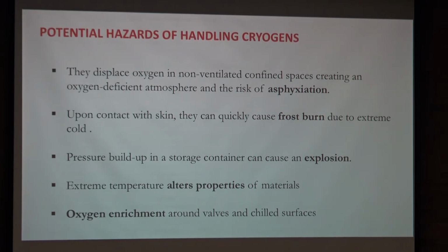When there is liquid evaporating, expanding into gas, and this gas cannot escape, then at some point you get into the regime where you run the risk that the vessel is actually exploding. Some of you may remember the Halloween tour we had a couple of years ago, where the building had to be evacuated due to a helium dewar that had a blocked exhaust.